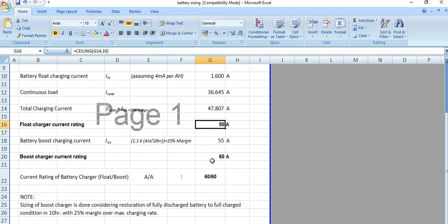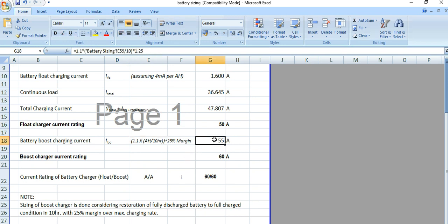Now for the boost charging current, the formula is 1.1 multiplied by ampere hour divided by 10 hours, because this is a C10 battery from the Exide manufacturer. Considering the 25% margin, it comes to 55 ampere.